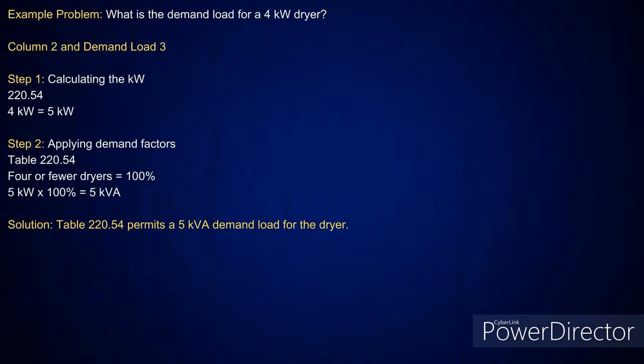So in this case, I've got a 4 kW dryer. I know I have to kick it up to at least 5 kW. And I have 1 or fewer, so I'm going to take it at 100%, and that's going to tell me the demand load here for the dryer is 5 kVA or 5,000 VA.